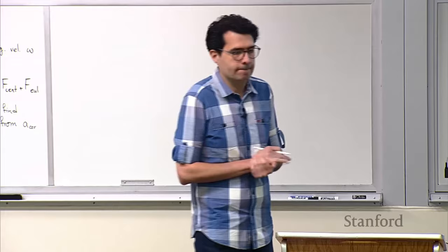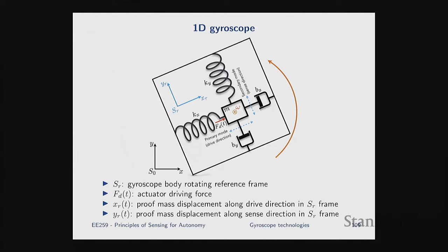Okay, so the answer is there are two very clever things in the design that help the device differentiate, or only be sensitive to, angular motion and not linear acceleration. Well, first thing is that you cannot fully decouple. So there is going to be a little bit of coupling from external linear acceleration to the device, and it's going to look like a little bit of added noise if there's external acceleration applied. But most of it you can fully filter out by two things.